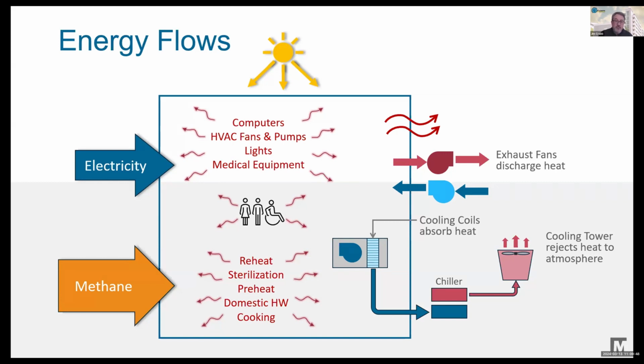So the main way heat comes out of our building is through the cooling system. Mostly it goes out through a cooling tower, which rejects that heat to the atmosphere. Our mechanical systems are also ventilating the building, so the exhaust fans discharge heat. But some of you engineers in the audience are thinking, wait, in the winter I don't use a cooling tower, I don't run my chiller, I use free cooling.